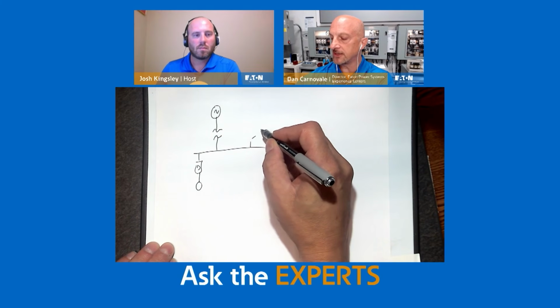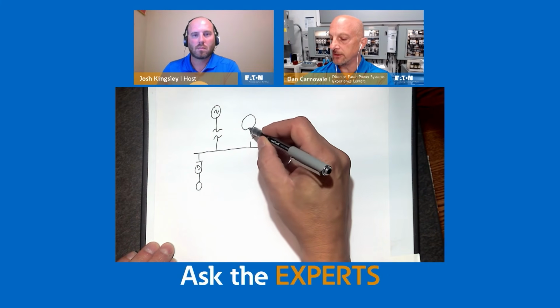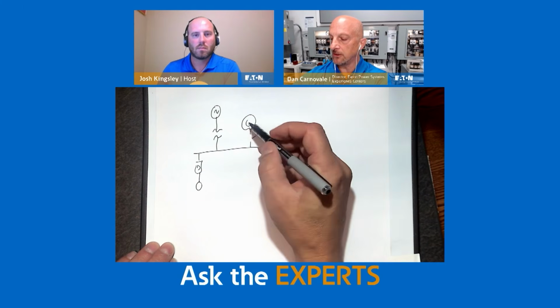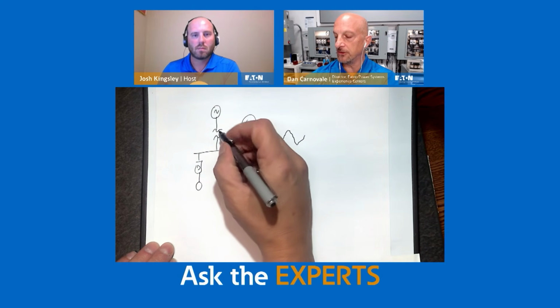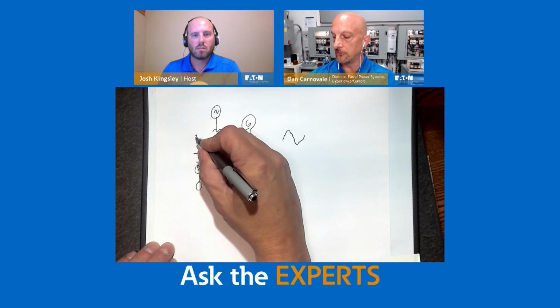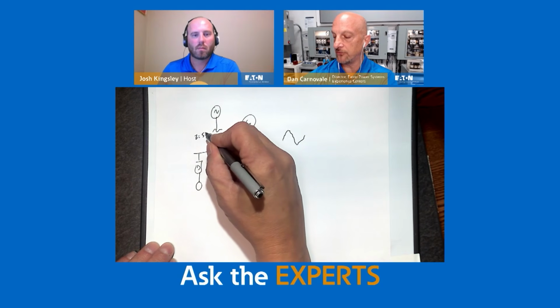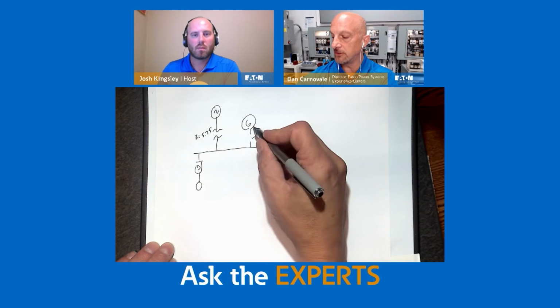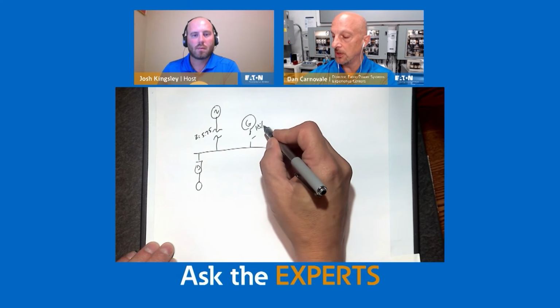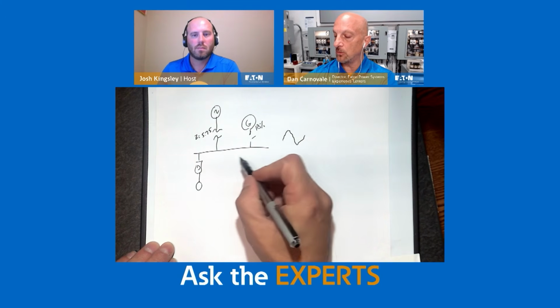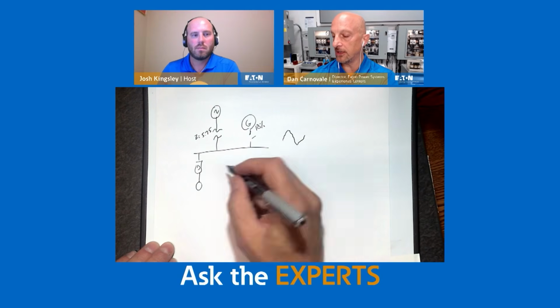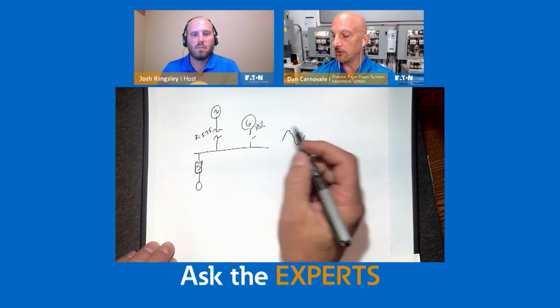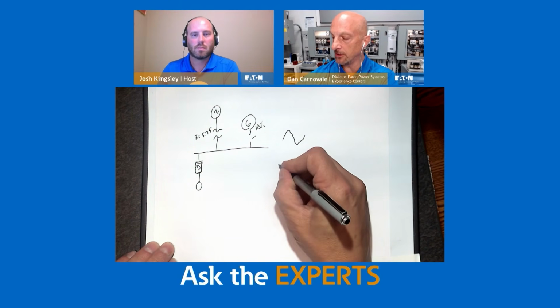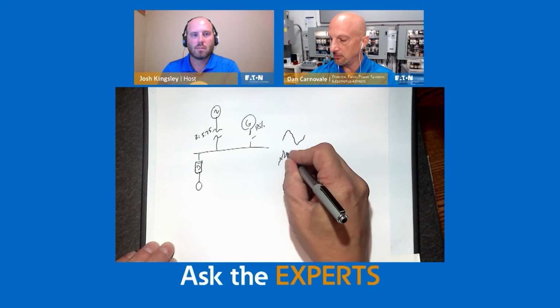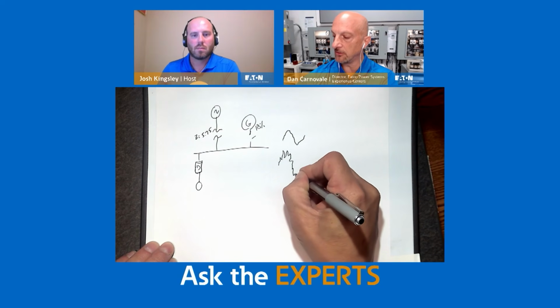What we've seen in the past is, you have a generator here, and when you're running on the normal source, this utility source transformer is 5.75% or something like that. Generator impedance looking back into it is 18%. So as I look at what I'm going to do to take care of the harmonic issue, well, maybe when I'm running on my normal source, it looks like that. But when I'm running on my generator source, my voltage distortion really gets kind of crazy.